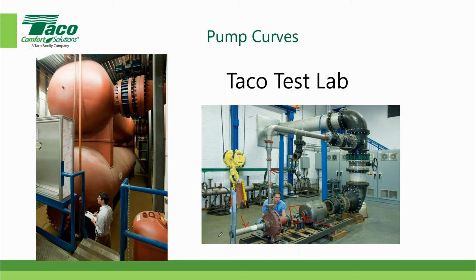Now, what you don't see in this photograph, I'll show you another photograph, is that there will be a flow meter that can measure the flow in gallons per minute. So now we have the 4 pieces of information. We have the flow in gallons per minute, the suction pressure, the discharge pressure, and the power input to the pump shaft.